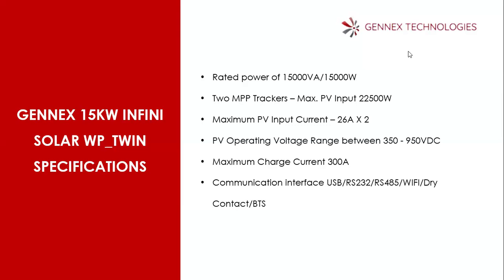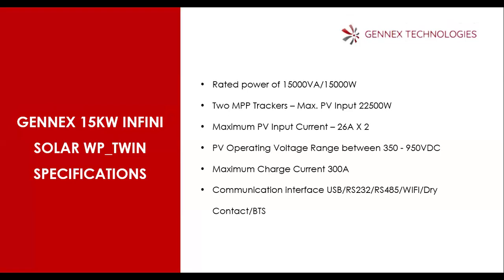Each terminal has an input current of about 26 amps, which means if you have a solar panel rated around 12 amps or 13 amps, you can have about 2 strings of it on a terminal. And the voltage range is very wide, which allows you to use more solar panels. You can connect up to 950 volts.